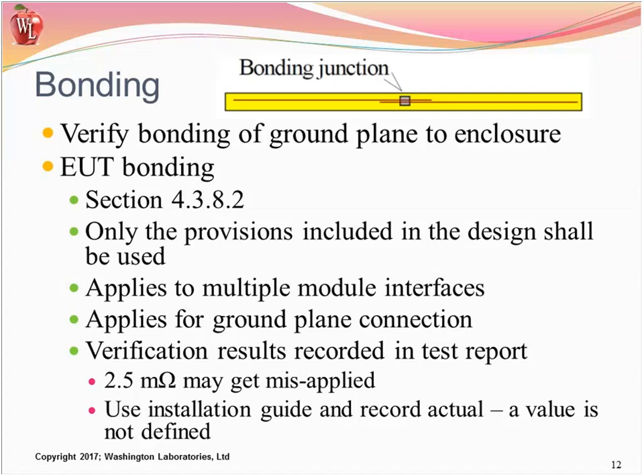Now, if you have a shielded cable that must be installed, no ifs, ands, or buts, it's not an optional cable, it's there, then you may be able to include that as part of your grounding scheme, only if it's going to be grounded that way in the real installation. So don't put artificial things in here. And we can apply this to a lot of cases. Remember, it applies to the ground plane connection, not necessarily 2.5 milliohms. This 2.5 milliohm requirement throughout history has been misapplied over and over again.